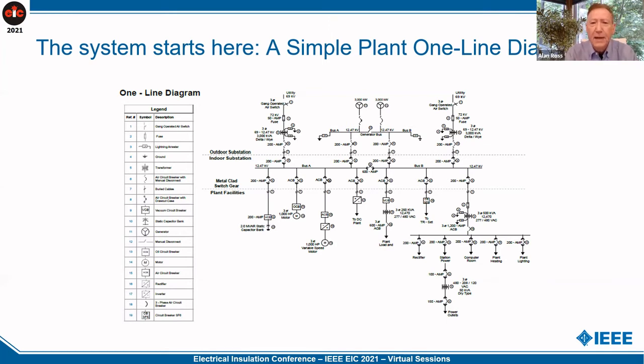How many of you have added new assets into the system? Every one of them raised their hand. How many of you have redone your one-line diagram in the last 2 years? About 1/3 of them. The rule of thumb is if you add assets to a system, you've got to redo your one-line diagram, and you've got to do an arc flash study every 2 years.